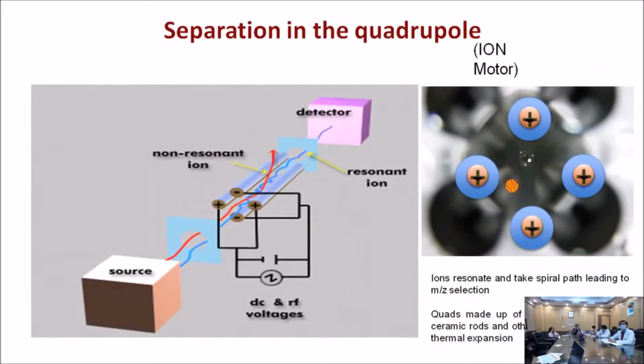Now, the separation in the quadrupole. After ionizing, the pseudomolecular ions enter the quadrupoles. What you see here is that, like an electric motor, oppositely charged fields are formed using a suitable radio frequency combined with DC voltage.